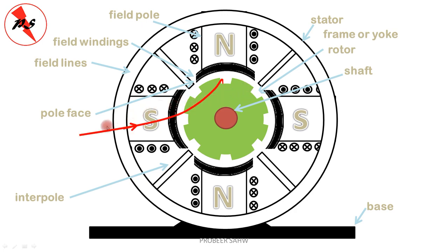Now what we do is take a wire and wrap it around these slots to create the armature winding. We take a wire and go to this slot, then take that wire out from this slot and put it back into this slot again, and take this out from this slot, and it is returned back.